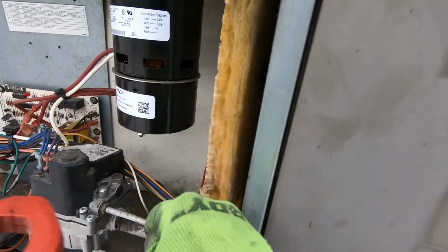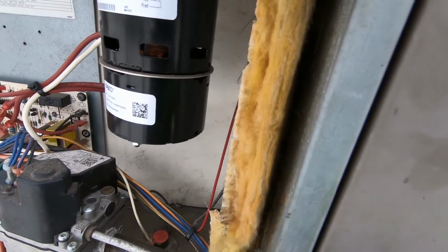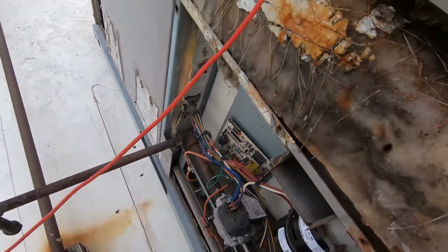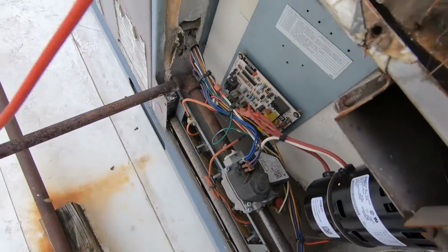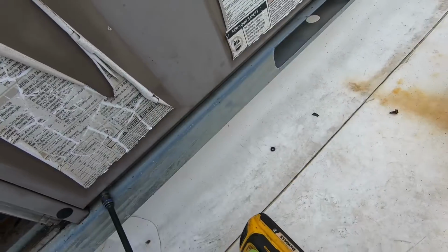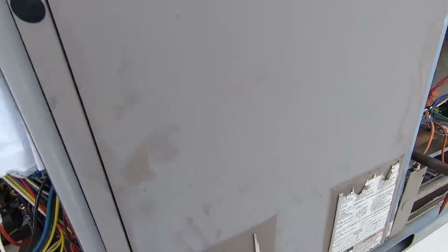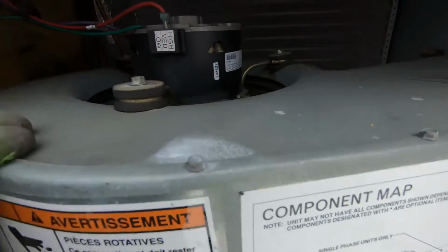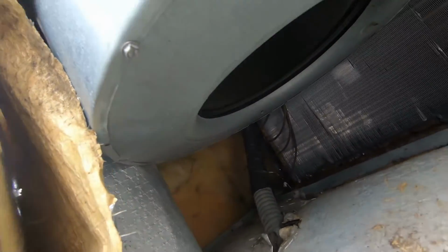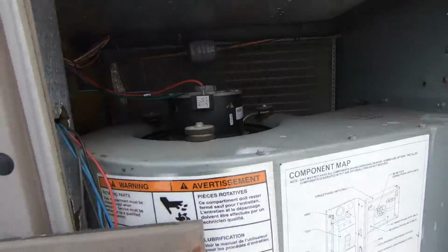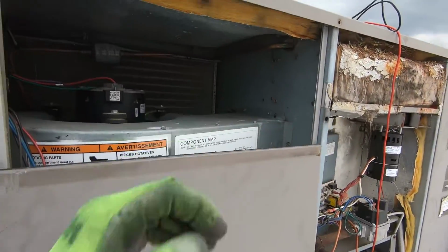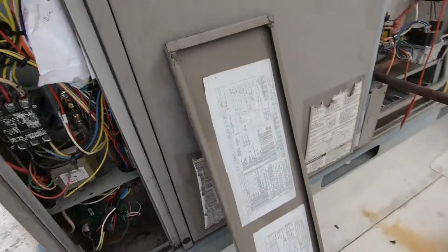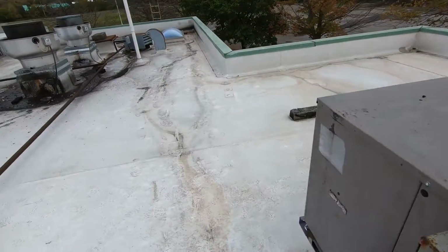All right, that's not saying that rollout wasn't opening and hadn't opened a certain amount of times to lock out our heating ignition control board. Open up the blower compartment here. Our blower is running, that's good. And I don't see any other limits or anything in here. So I'm gonna shut the power off and we're gonna inspect the heat exchanger.